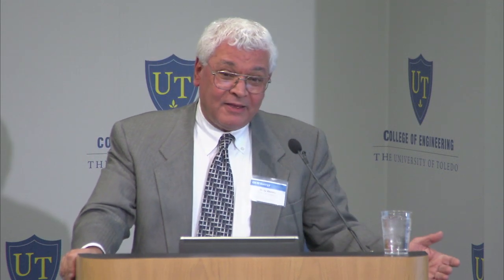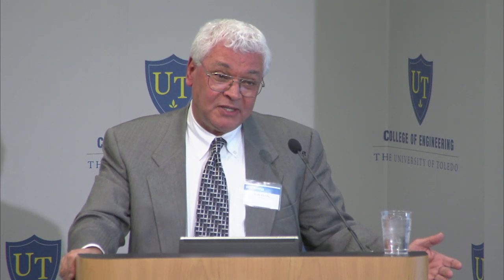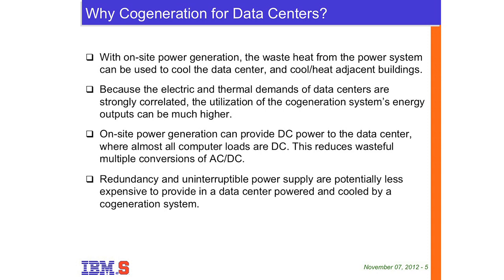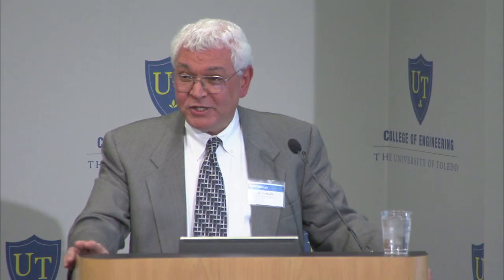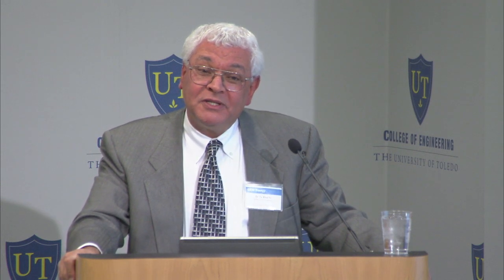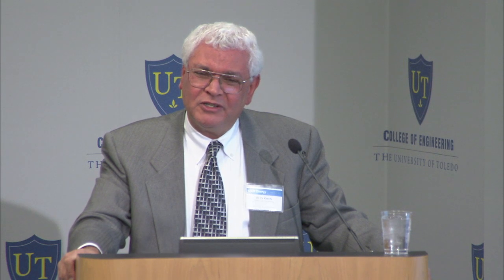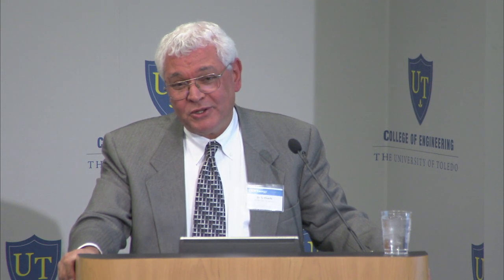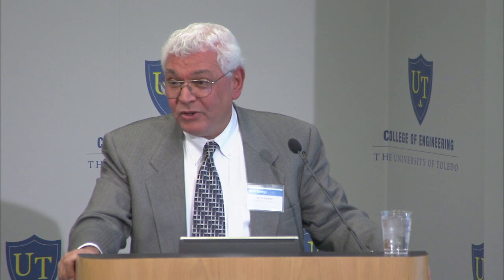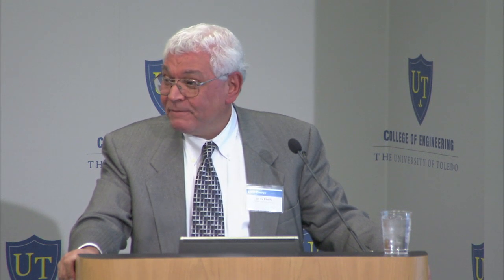When you have cogeneration systems on site, you can build redundancies into the system itself that obviate the need for backup diesel generators and things of that sort. In our case, the worst that can happen to us, aside from equipment failure which is handled through redundancy, is an interruption—not of electricity, but of natural gas. But if you have an interruption of natural gas, you can always have a tank containing a substitute, in our case propane, that can run the system for several days until they fix the gas line. So you have built-in redundancies that can reduce the capital cost of the equipment because of the configuration of the system.